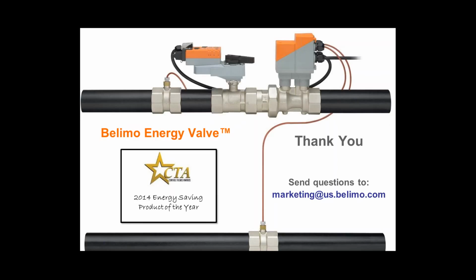One other question here is, in your example on the screen, how many hours of the year was the coil oversupplying? It was the gray part of the screen you showed where the BTU valve would save energy. I don't know that I have year-over-year data on the specific examples that I use, so if I gave you a number, I would just be making it up, and I don't want to do that. The reality is that what we see, and I'll use chilled water as an example, is that we typically see large delta T problems in the shoulder seasons and into the high demand seasons, and then it seems to improve in high demand seasons, which actually makes sense. The higher your load is, the harder it is to overflow your coil because you have so much load.